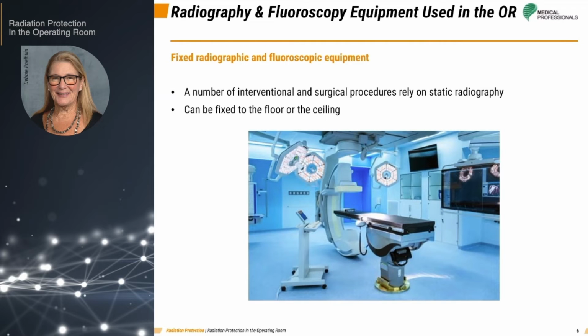The decision for which equipment is stationary or mobile is determined during the planning and design of the hybrid operating room, and this is based on a number of factors, including the size of the room. The Facility Guidelines Institute requires that there be at least 600 square feet of open floor space in hybrid ORs. So let's talk about fixed equipment first.